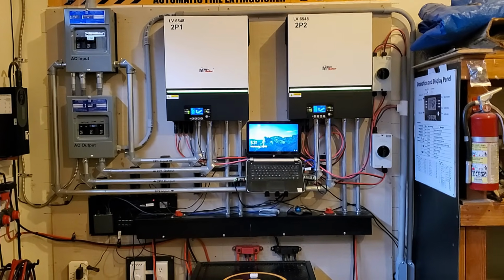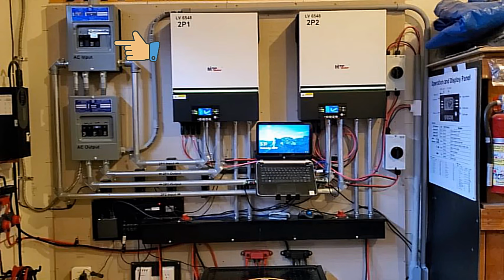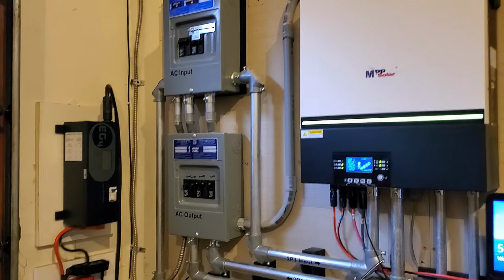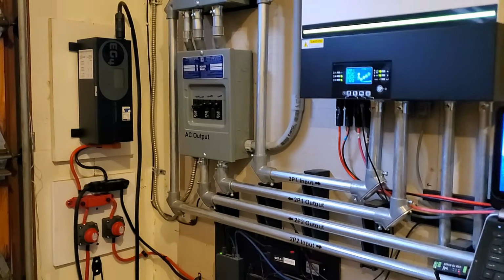To the left of the inverters is the input subpanel, which handles the grid connection. And just below that, the output subpanel, which routes power from the inverters to the main house panel. On the far right are two IMO disconnect switches mounted at the inverters. These provide a quick and accessible way to isolate the solar arrays if they need to be shut down. Over on the left wall is the EG4 chargeverter charging station, which serves two important functions.